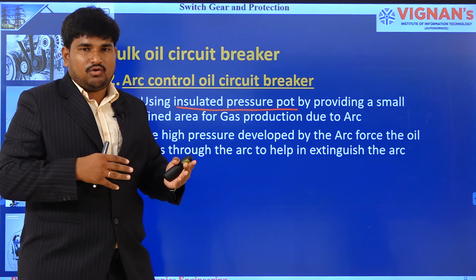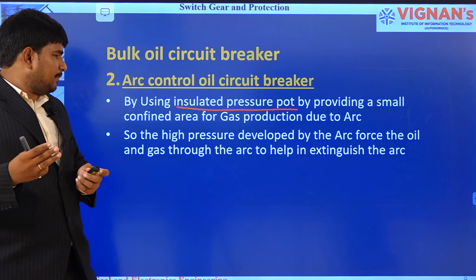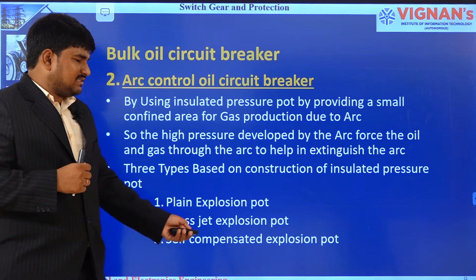As the gas increases, the pressure of the gas also increases. Due to the pressure, when the moving contact is moving away from the fixed contact, the pressurized gas forces the arc to be quenched, to be extinguished. That is the added advantage in the arc control oil circuit breaker. Based on this insulated pressure pot construction, there are 3 types of oil circuit breakers: plain explosion pot, cross jet explosion pot type, and self compensated explosion pot type. Let us go into detail of each one.